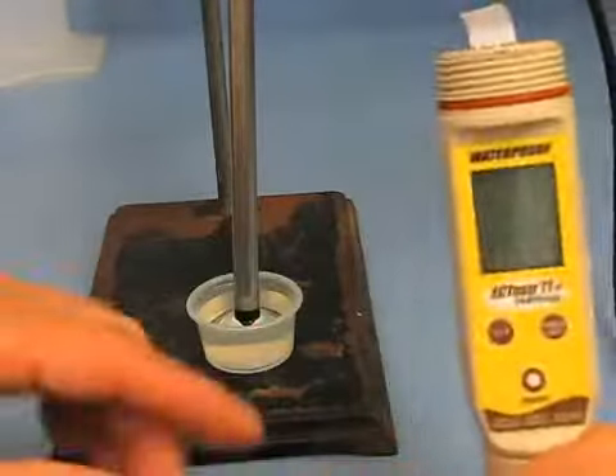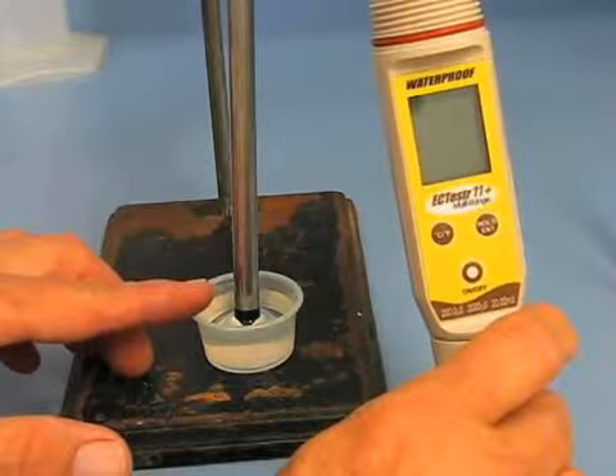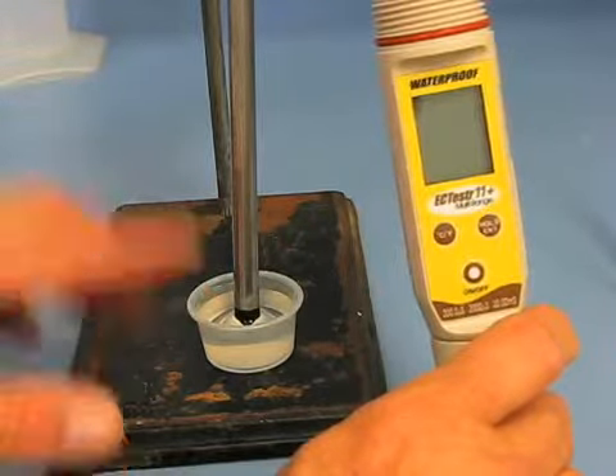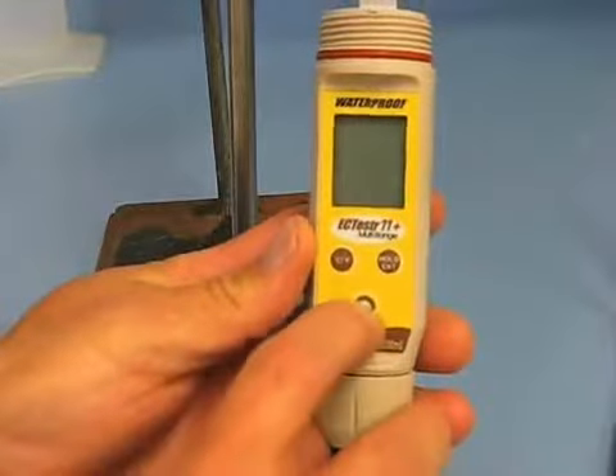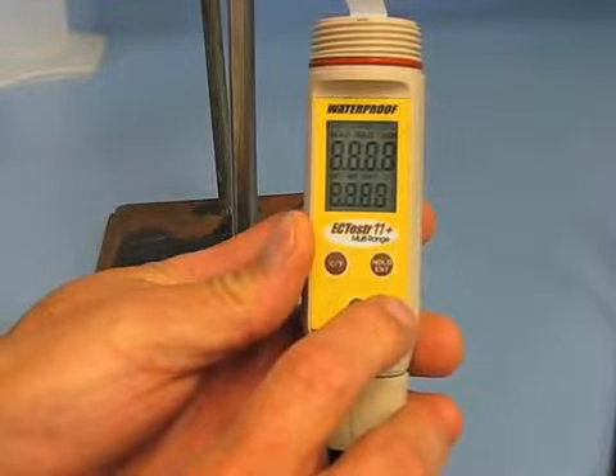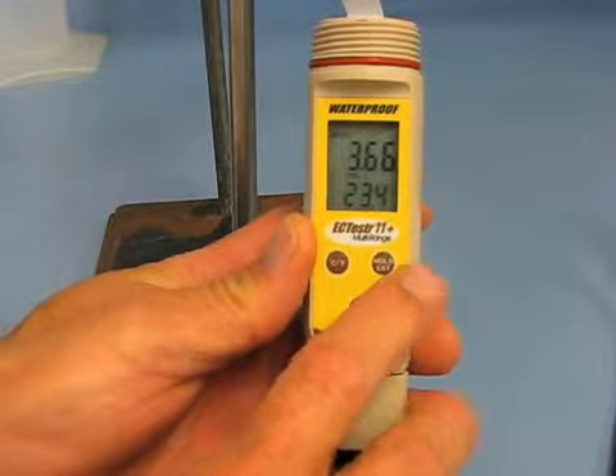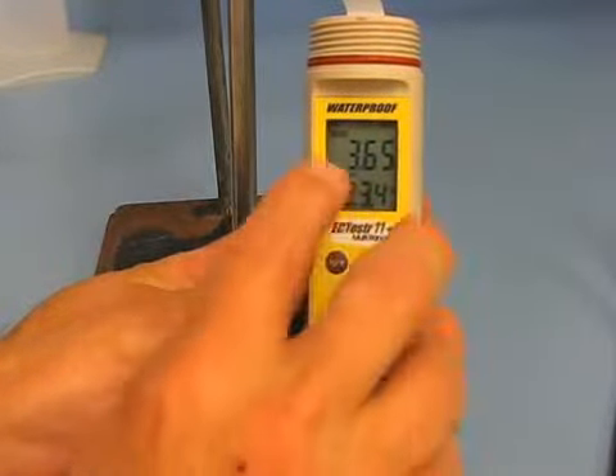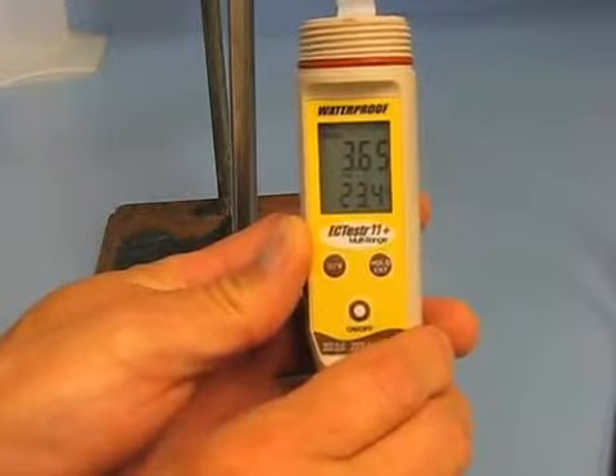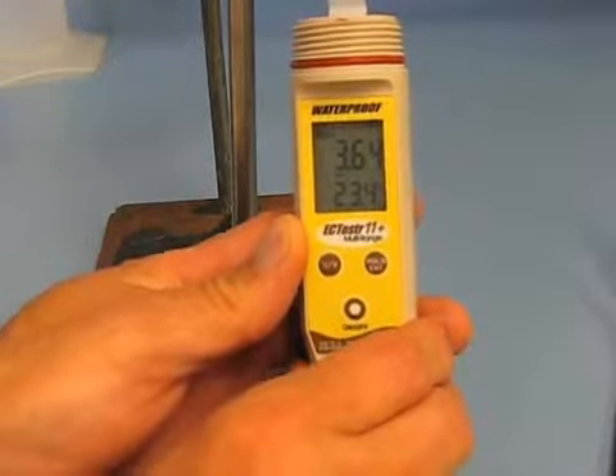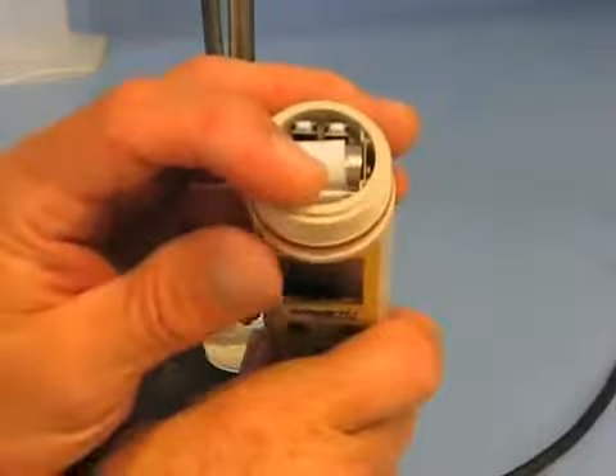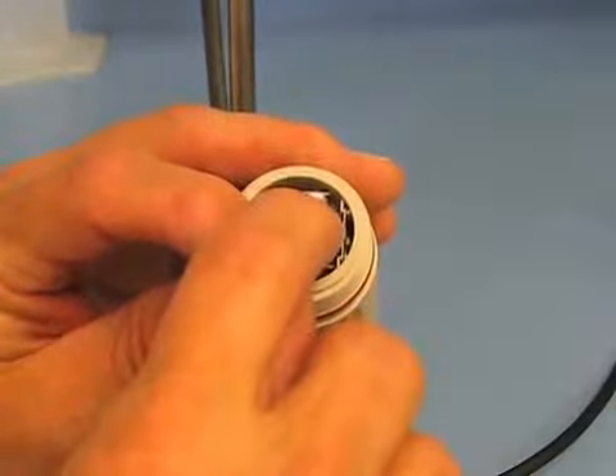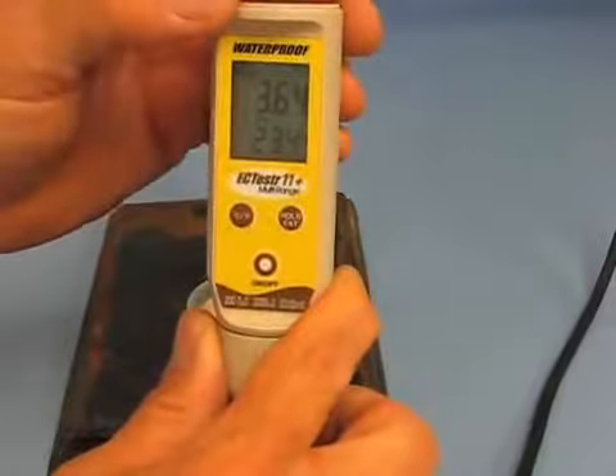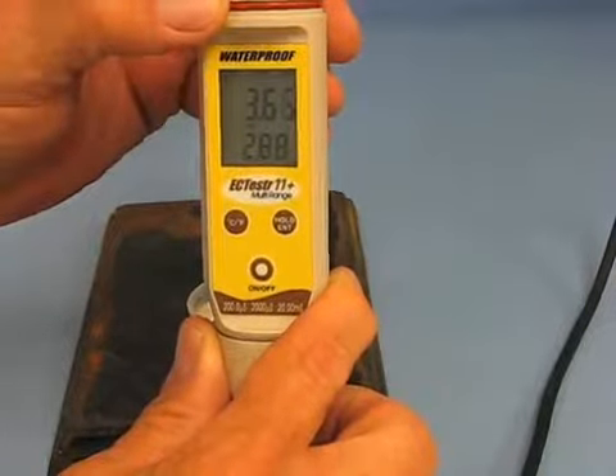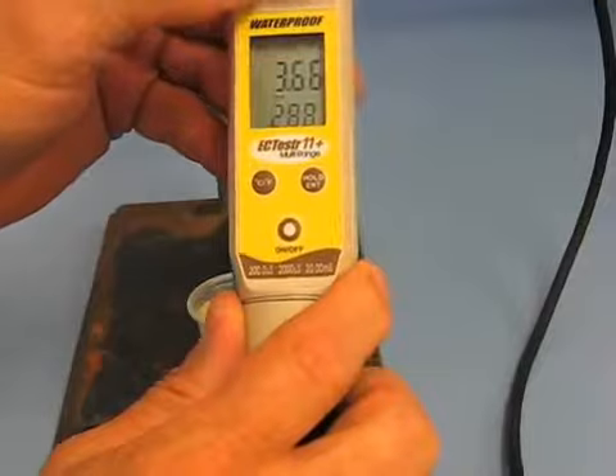For convenience, I've placed the probe into the 2.76 calibration solution so I can use both hands to work with the meter. But if you turn the meter on, we'll see that it's reading 3.65 millisiemens per centimeter. That is the same as decisiemens per meter, which we use frequently here at Pace. If you look at the top, we need to drop those numbers down. So we have the increase button on the right, decrease button on the left. If you don't remember which one it is, it doesn't matter, because if you press the increase button, you'll see the numbers go up. If you press the decrease button on the left, it'll go down.